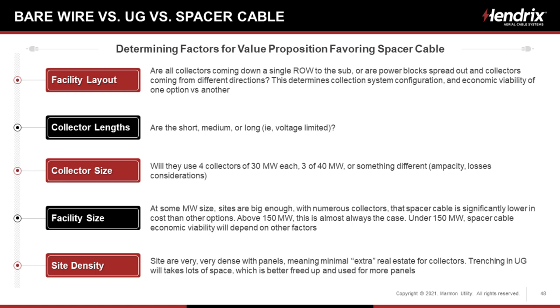If I have 200 or 150 or 250 megawatts laid out a mile from the substation, and all of those collectors are coming down a straight line, slam dunk, spacer cable gives you a massive economic value proposition. Collector lengths, are they short, medium, or long? Are they voltage limited? Are they loss limited, etc.? These are things we have to look at.